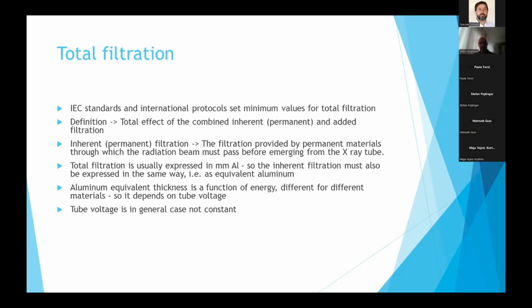So you're usually expressing it as quality equivalent filtration. And then you need to decide on the material in terms of which you want to express it. Usually it is aluminum, of course, similar to HVL. And the problem is that aluminum equivalent filtration is dependent on radiation quality. So you need to decide for which energy or which tube voltage you want to express it, and which material, etc. So the definition is not clear. And also the way that you standardize measurements and calibrations is not clear.